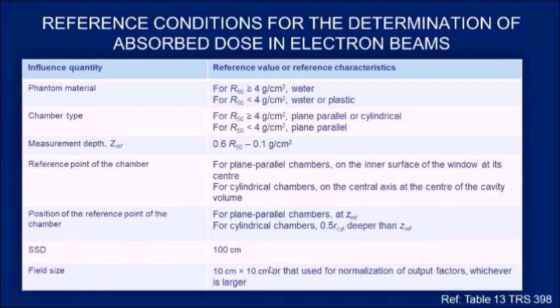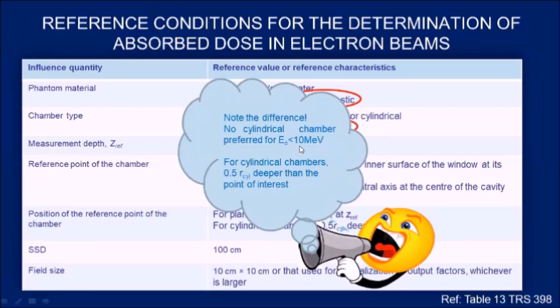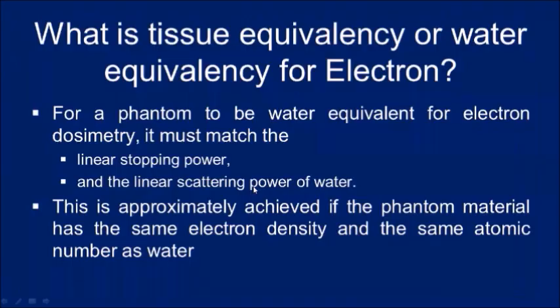SSD should be 100 cm and field size is usually 10×10 or the field size used as reference for output factors. Please note: no cylindrical chamber is preferred for less than 10 MeV, and for cylindrical chambers the position should be 0.5R deeper than the point of interest Z_ref.